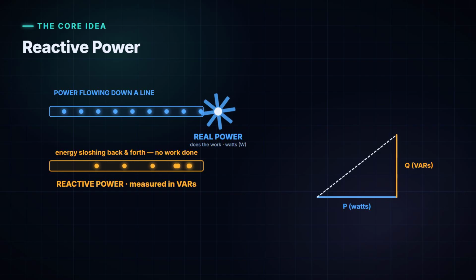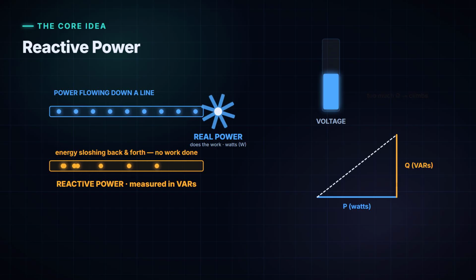And this is the important part. When the grid is short on reactive power, the voltage drops. When there's too much, the voltage climbs. So if you can control reactive power on demand, you can control voltage. Hold on to that idea. It's the whole point of everything that follows.